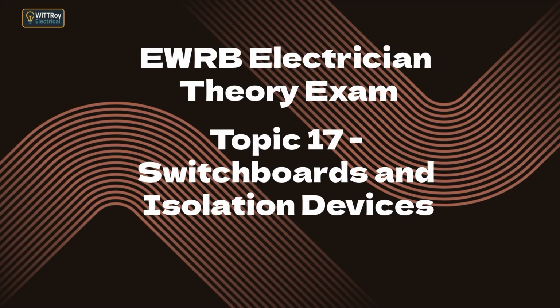Some installations require fire-resistant barriers or separation between switchboard compartments. The environment and mechanical conditions must be considered. This includes the level of dust, moisture, heat, chemicals, vibration, and potential mechanical impact. The board must have an enclosure rating suitable for the conditions, such as indoor, outdoor, wet areas, or corrosive environments.